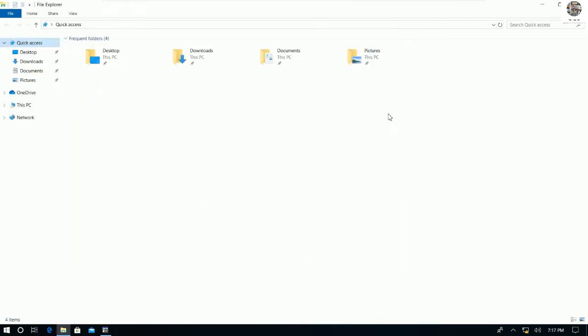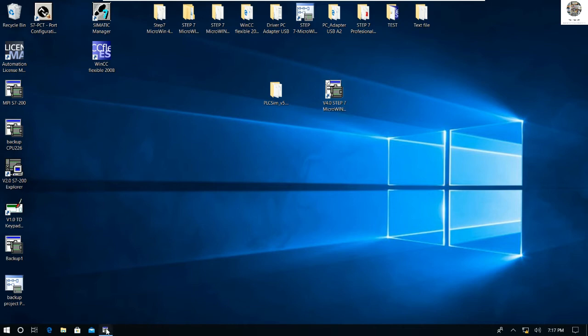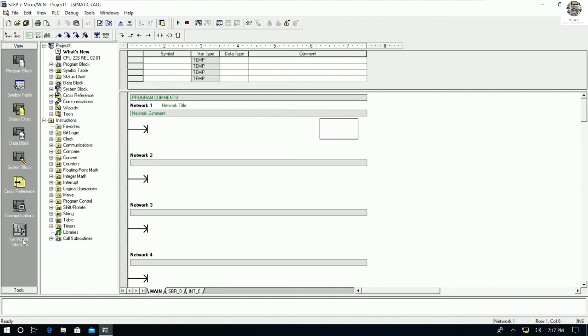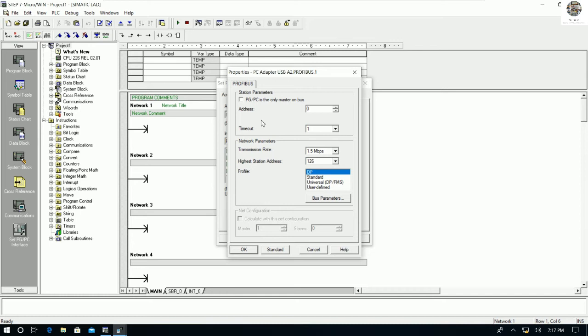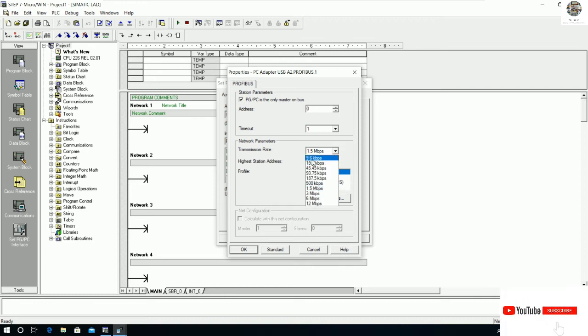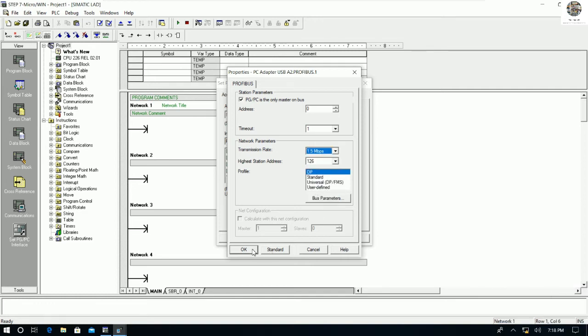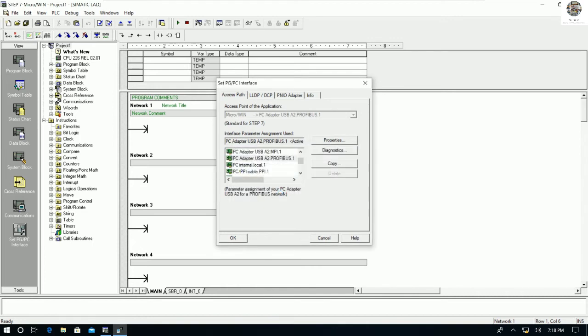Now go back to the software and open Set PG/PC Interface. Select PC Adapter USB A2 Profibus and click Properties. Here we need to check that the PG/PC interface is set as the only master on the bus. Then we need to match the baud rate — if we choose another baud rate, for example 1.5 megabits, let's check what happens.